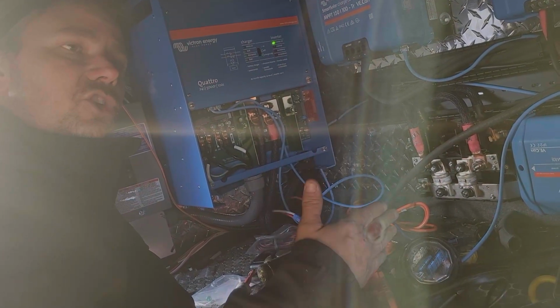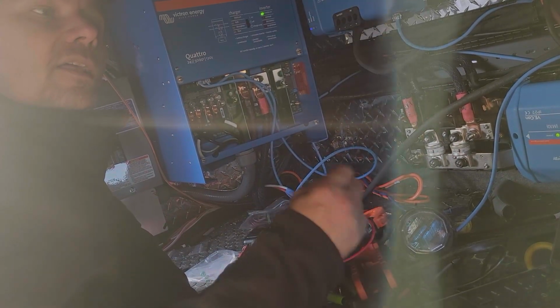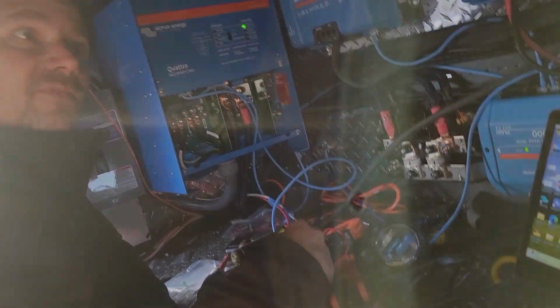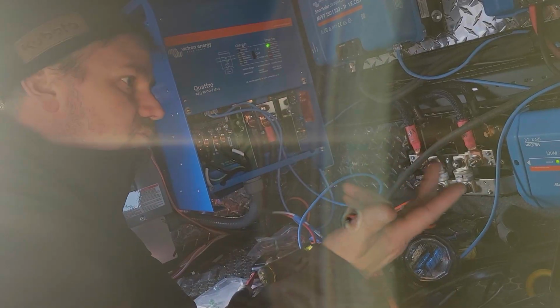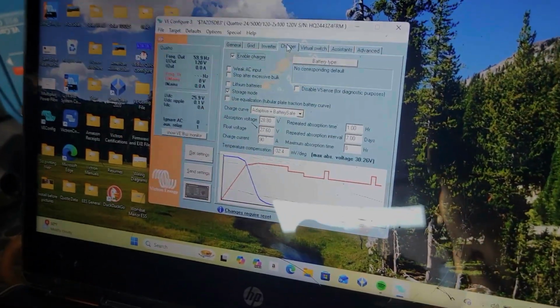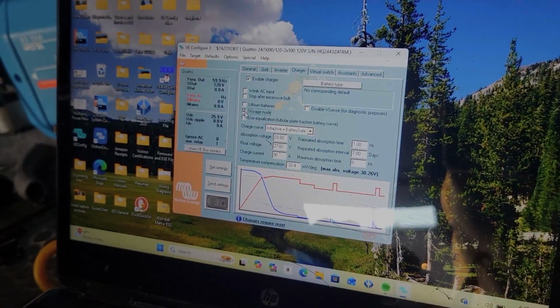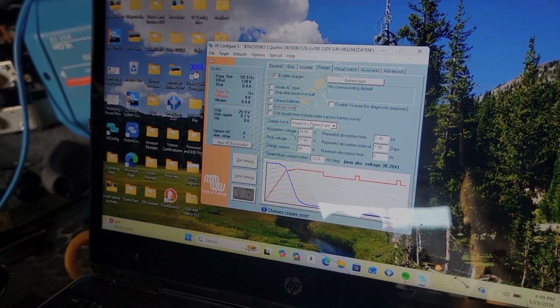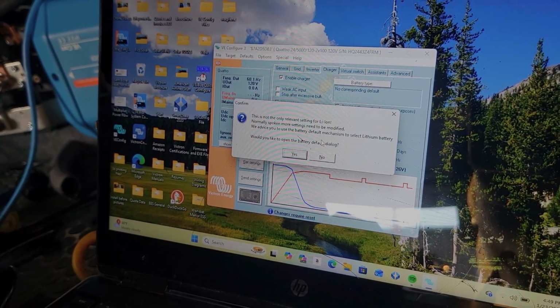We don't want to get there, but we also want the inverters to shut down before the batteries shut down and the BMS shuts down. That voltage is typically 10.5, which would translate to 21 volts on a 24 volt system. So that's how that works. We want this system to shut off before the batteries shut off. All right, next step, we take it out of storage mode and we enable lithium batteries.